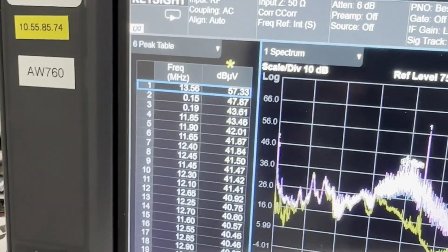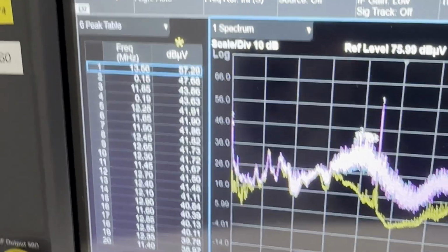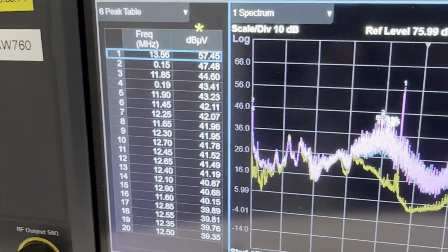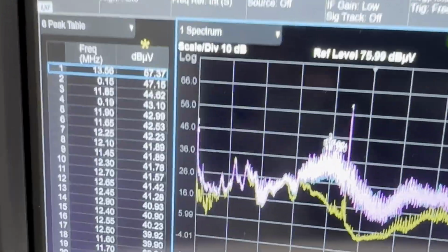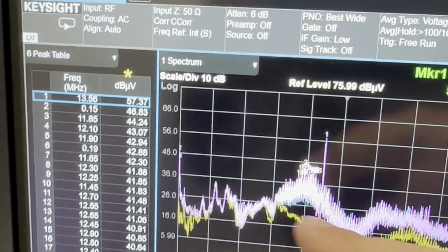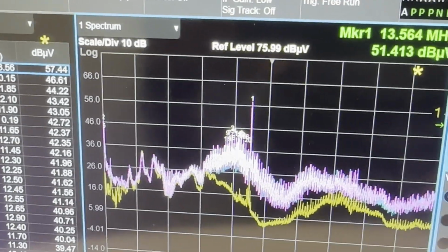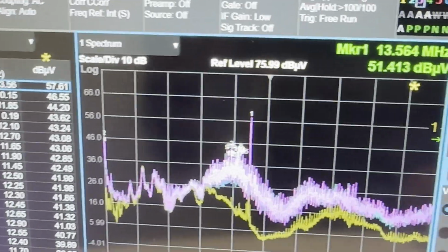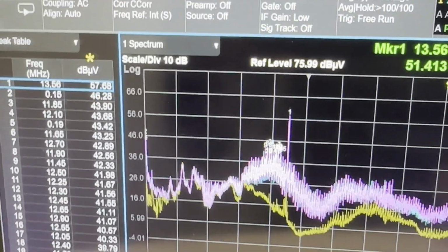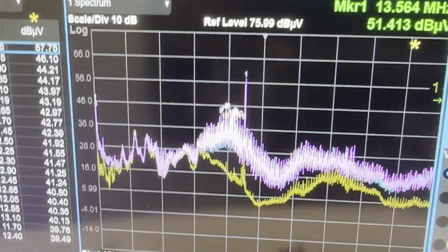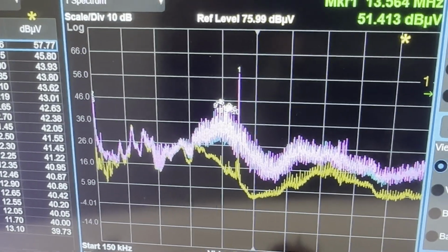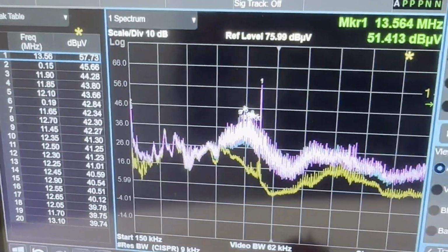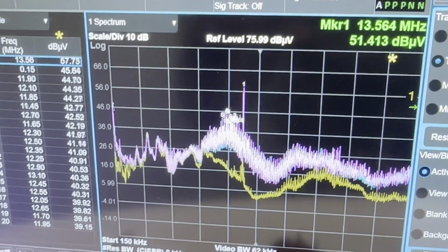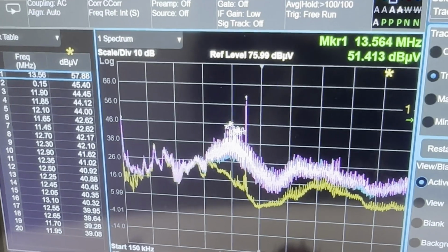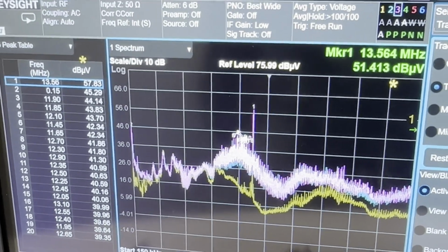and so on. So the peak 2 is at 150 kilohertz, and you can see it there, but I know this is also caused by poor calibration on this particular LISN, so I'm not too worried about it. In essence, you can see that most of it is matching the noise floor, and most of the emissions actually are coming very low, and this isn't any kind of concern, so I'm quite confident that this device is going to pass the conducted emissions test now. So that is an example of pre-compliance with the AC LISN. I do apologize.